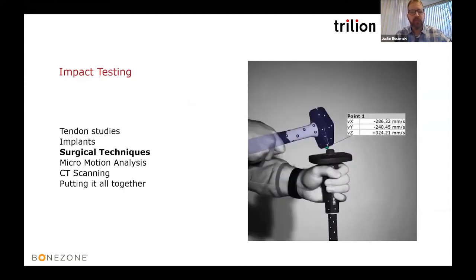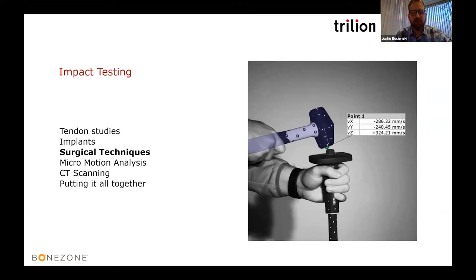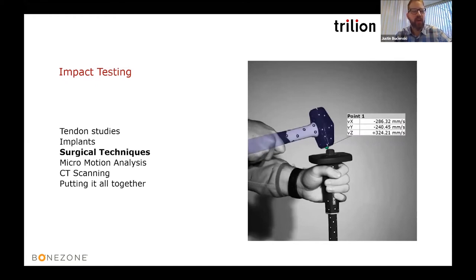Let's now turn to a couple of different surgical techniques. The first is an impact test involving a hammer strike — a high-speed event that needs to be understood to best control for implant placement. Some orthopedic surgery requires that pieces be implanted using hammer blows, and understanding the variability of force ranges and durations of those blows is critical for balancing implant stability without risking bone fracture. The objective of this simulated test was to monitor the hammer strike including six degrees of freedom and pinpoint the impact location temporally and spatially.